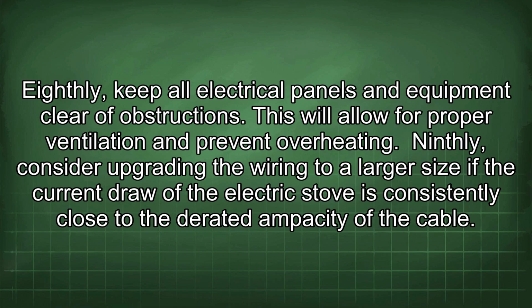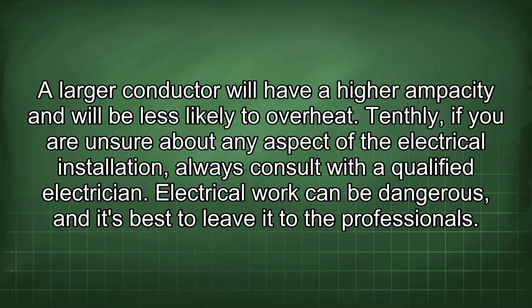Ninthly, consider upgrading the wiring to a larger size if the current draw of the electric stove is consistently close to the derated ampacity of the cable. A larger conductor will have a higher ampacity and will be less likely to overheat. Tenthly, if you are unsure about any aspect of the electrical installation, always consult with a qualified electrician. Electrical work can be dangerous, and it's best to leave it to the professionals.